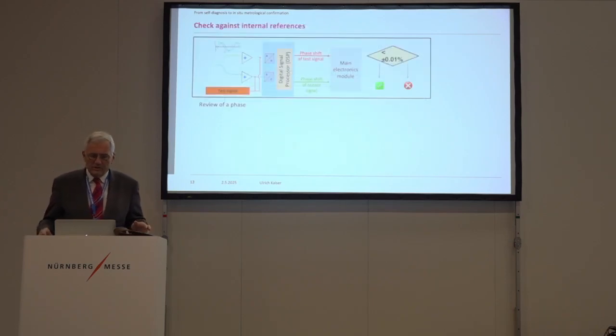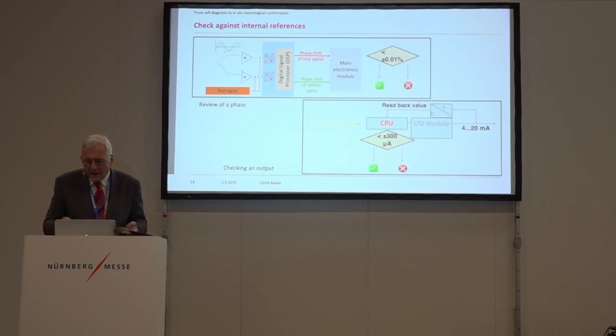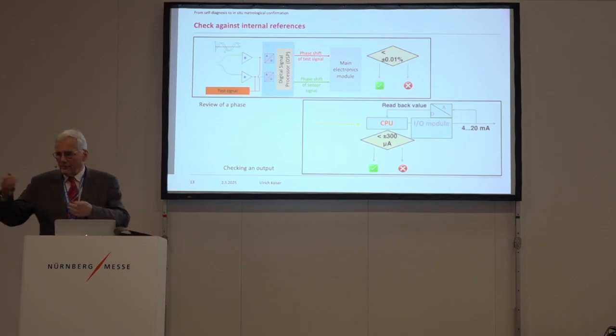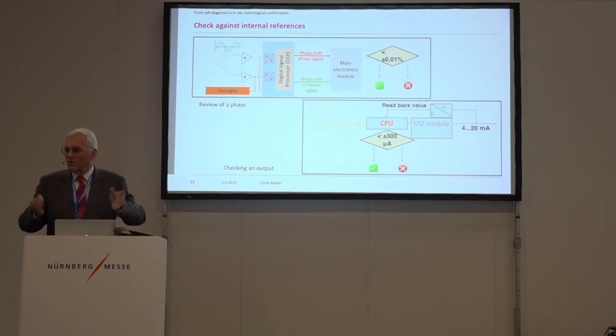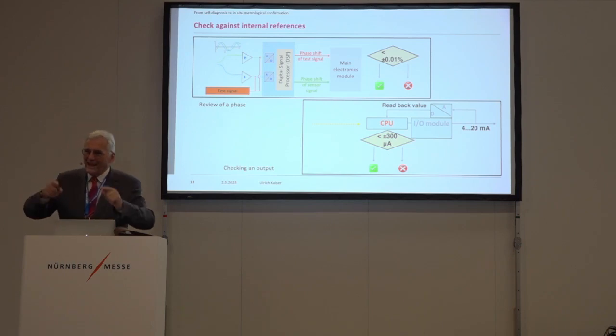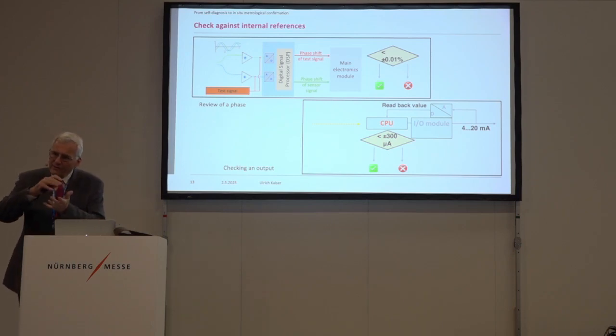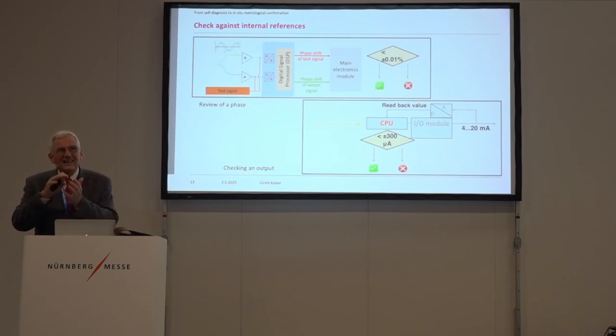Then you check against an internal reference, for example a phase. You have a phase measurement, and you also have a system to measure the phase. Or you have an output - you have an amplifier and check what's getting into it compared to what's coming out. You may have something to measure a voltage. But the important thing is you cannot check everything in a process sensor - you only grab a fraction of all the metrological quality determining parameters, not 100% of them.